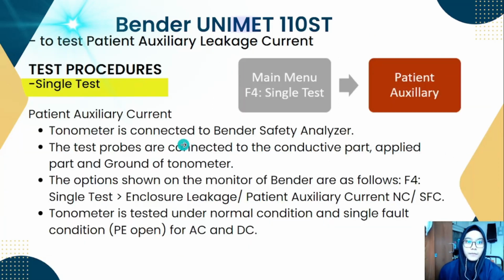The next one is we use the Bender to test the patient auxiliary leakage current, where we use the single test. For this one, the tonometer is connected to the Bender safety analyzer, and the test probe connected to the conductive part, applied part, and the ground of the tonometer, same as the previous one. Then the only difference is the option that we choose on the monitor of the Bender. So in the main menu, we choose the single test, then we choose the patient auxiliary current, where it will be tested under normal condition and the single fault condition.